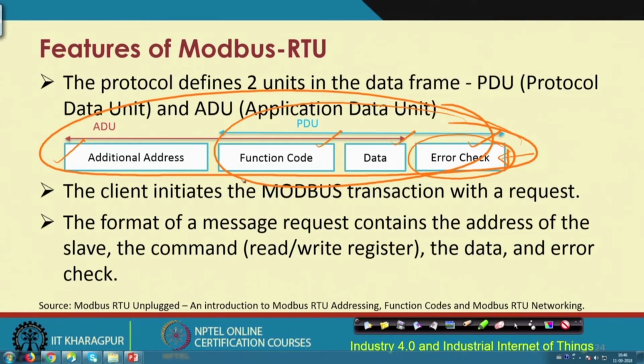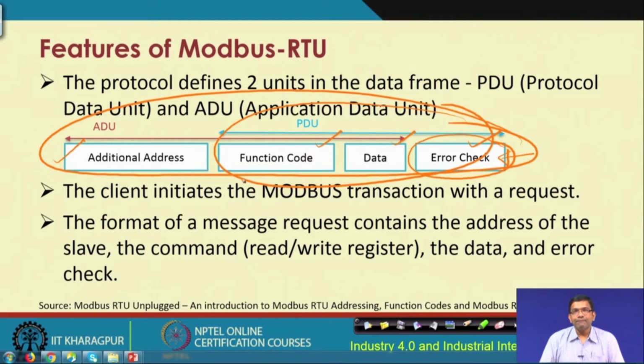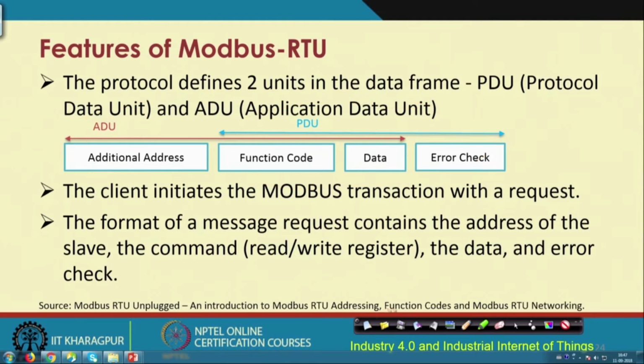So, basically in this kind of communication, the client initiates the Modbus transaction with a particular request, and the format of a message request contains the address of the slave, the read write register, the data, and the error check.